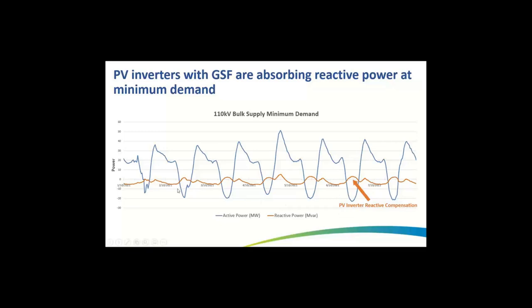Another thing to note that's been observed increasingly in distribution networks internationally is the increasing capacitance on the network, and you can see that happening consistently overnight, where the VARs are negative as a result of that capacitance on the network. And this is thought to be a result of the increasing power electronic devices and improving power factor of many loads on our networks.